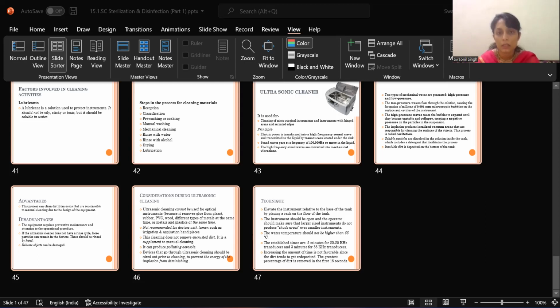Now, how do we control the sterilization process for a hot air oven? For this, spores of non-toxic strains of Clostridium tetani are used. Paper strips impregnated with 10 to the power of 6 spores are sterilized and inoculated in thioglycolate media and incubated for sterility tests under strict anaerobic conditions for 5 days at 37 degrees. Or Browne's tubes can be used, which show a green color after sterilization, or thermocouples can be used.